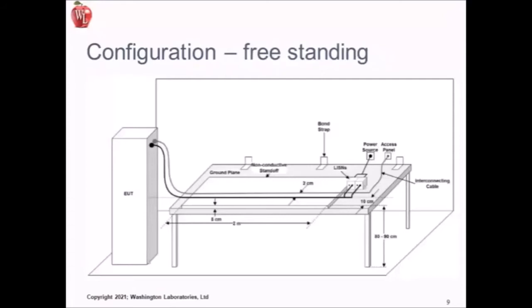This is an example of a freestanding or a non-tabletop type of equipment. You can see the EUT, or equipment under test, on the left is a larger rack or something like that that wouldn't normally be installed on the plane. But again, the general configuration is the same: bonding the enclosure to the ground plane, having LISNs mounted to the ground plane, and a certain amount of cable spacing to get that desired consistency.